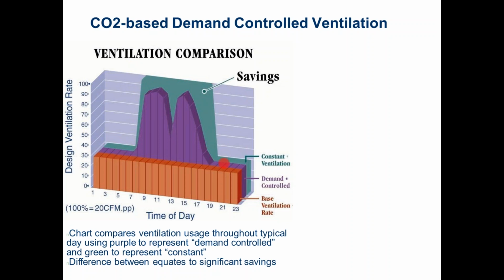So that green hashed area is the normal code required air. Purple is what would happen if I was tracking the amount of people that actually showed up, right? Some people come into work late. Some people check out and go to lunch early. Some people stay at the office at lunch. Some leave. Some never come back from lunch at all because they don't feel like it. And then some of them cut out early and go golfing, right? It's a typical office building, just a 2-hump type scenario. Everything between purple and green is energy savings because I'm not 100% occupied. I should be able to save energy there, right?